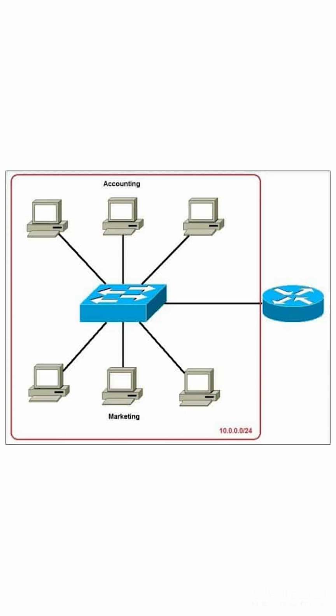Let's be clear, we're talking about an IT router and an IT switch. A BACnet router is very, very different than an IT router. A switch connects multiple devices to each other. It ignores IP addresses. It doesn't know about the concept of IP subnets. And it really just acts as a conduit onto a highway with lots of lanes.